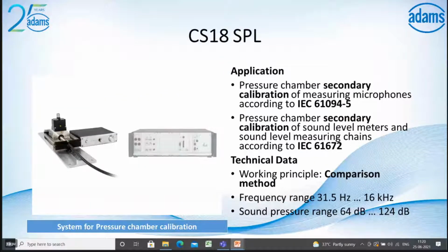For the pressure field microphone calibration, according to the standards IEC 61094 for working standard microphones, and IEC 61672 for pressure standard sound level meters. So it's a comparison method, a back-to-back calibration, with frequency range from 31.5 Hz to 16 kHz and sound pressure up to 124 dB that you are able to perform for the pressure field microphones.